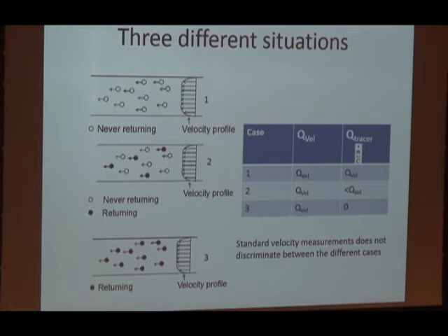Well, if I use the velocity method, shown up here, in all three cases, 1, 2, 3, I get the same answer. This standard velocity measurement doesn't differentiate between how the state is with respect to what was in this duct. But if we use the tracer gas method, for the first case, the tracer gas method gives the same result as this velocity-area method.